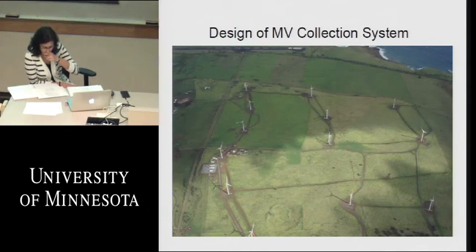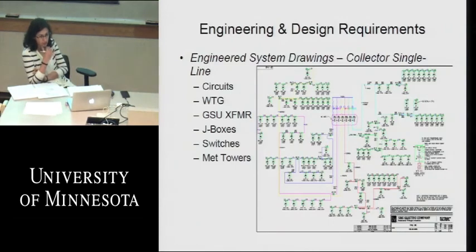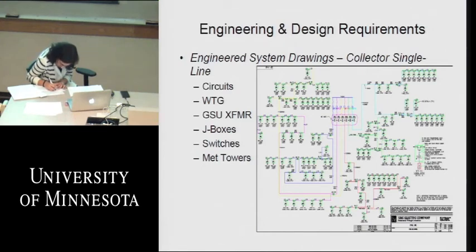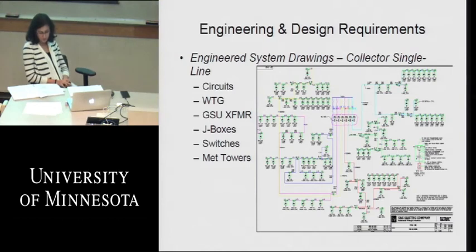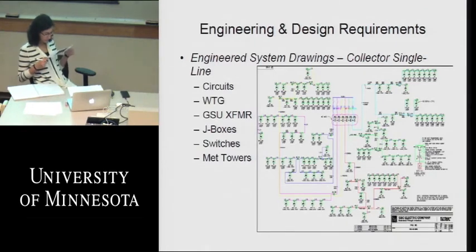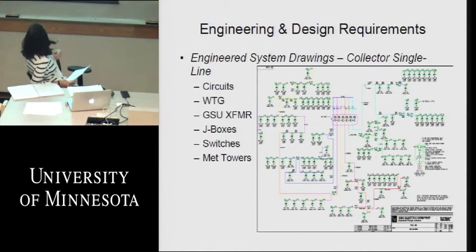And these are the kind of things we look at: the connecting circuits of the wind turbines up to the grid, the wind turbine itself, the generator step-up transformer within the wind turbine, a generator, and then a step-up transformer to go from medium voltage, that 35 kV, up to the 115 or 138 or 230 kV on the transmission system. We've got junction boxes scattered all around to connect all the components together, switches, and meteorological towers that measure the wind conditions on a real-time basis. So you see a single line diagram of a typical project, where all the green wind turbines are feeding in the colored radials into that collection bus in the middle that's blue and reddish.